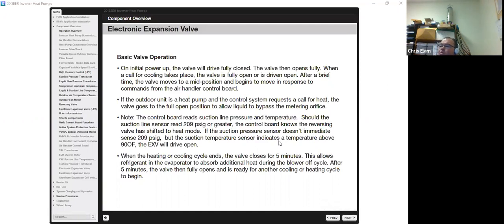When the heating or cooling cycle ends, the valve closes for 5 minutes. That's every cycle. This allows for refrigerant in the evaporator to absorb additional heat during the off cycle. After 5 minutes, the valve then fully opens. It then fully opens and is ready for another cycle, cooling or heat cycle.